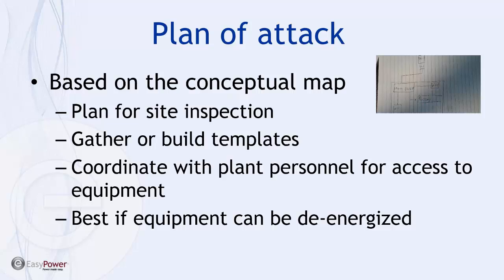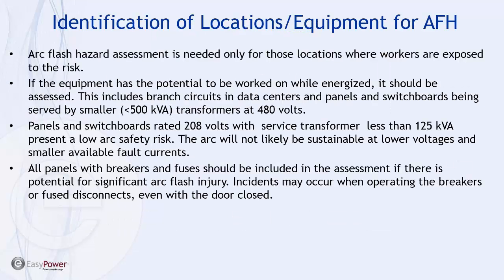If it's possible to de-energize the equipment, that's the preferred basis for doing data collection. Because at a first pass, it may take time and effort not only accessing the equipment, but finding the data, the labels, the nameplates — some of which can be a dangerous situation if the equipment is energized. If there's some way to coordinate the effort with scheduled shutdowns or off-shifts, make sure you build that into your schedule and plan of attack. You want this operation to be as safe as possible and not unnecessarily put people's safety at risk.